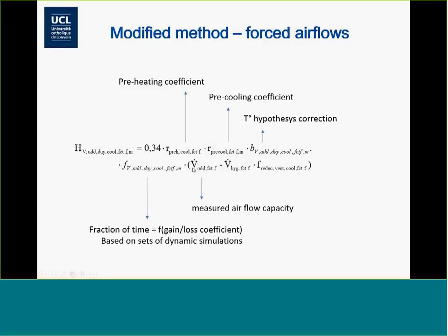If this value is set equal to the hygienic ventilation, of course the difference will be 0 and there will be no impact. We have some coefficients to correct this difference. This one is just like for natural ventilation, and we have coefficients dedicated to take into account pre-cooling strategies such as air heaters, heat exchangers, or adiabatic cooling, or things like that.